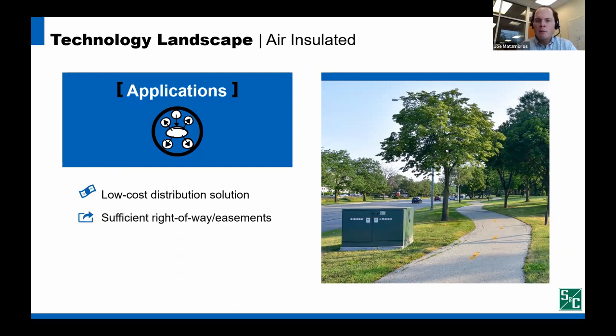The fact that it's been available for decades has resulted in utilities planning right-of-way and easements to support its footprint and operating practices clearances. Floodplains are not new, and planners have typically avoided siting air-insulated switchgear in high flood risk areas. That said, there may be more application points in your service area today that are prone to repeating 100-year floods.